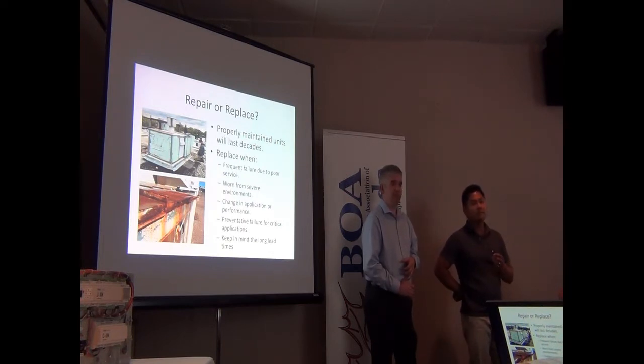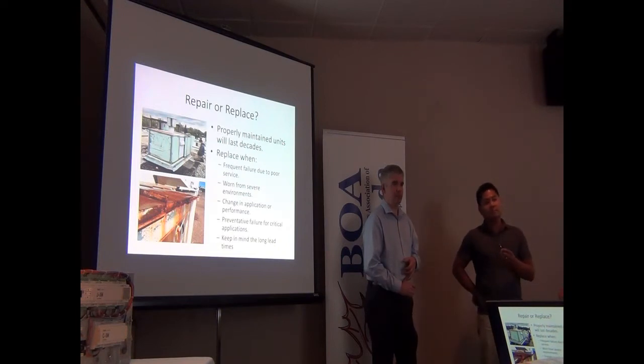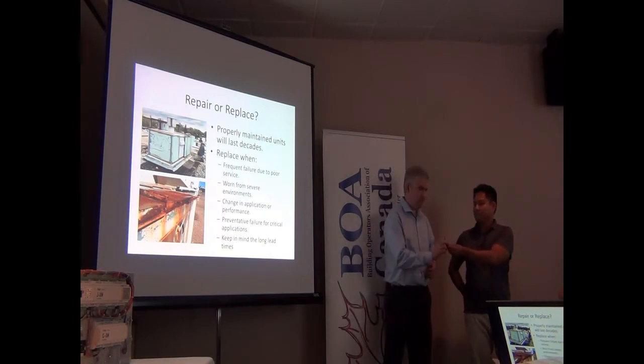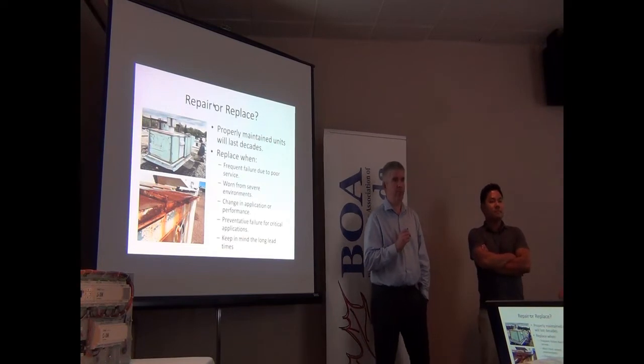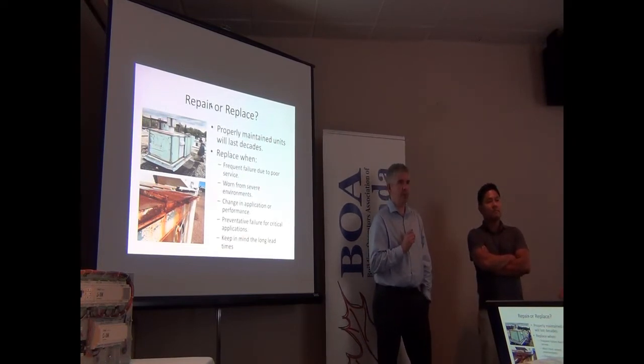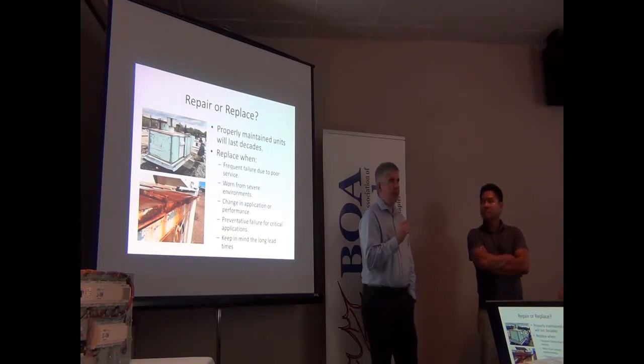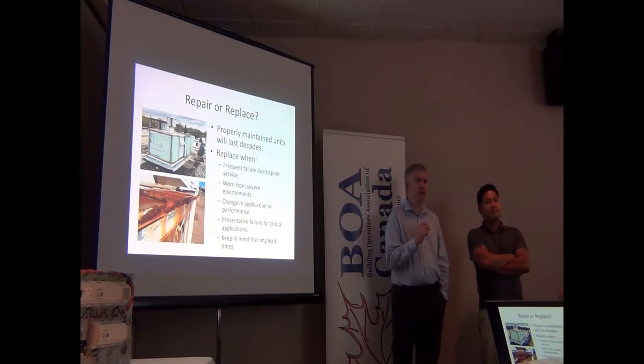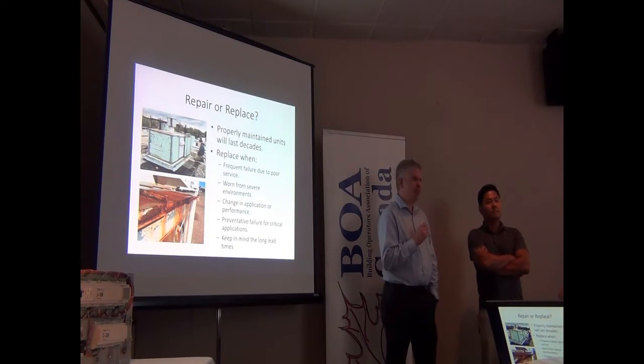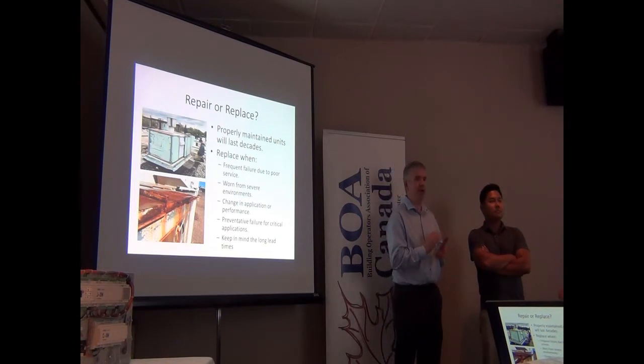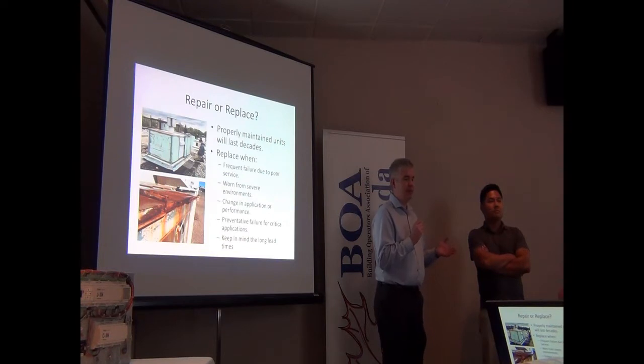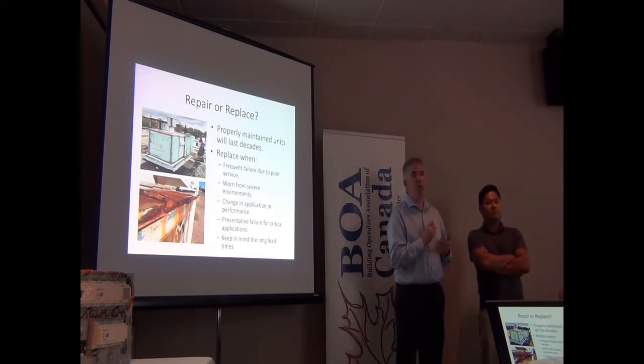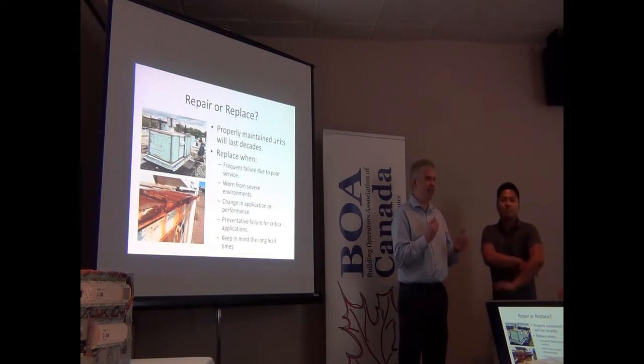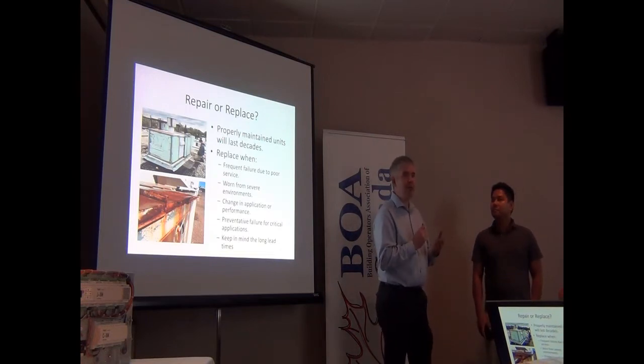You were talking about making changes to peripheral equipment. A lot of building operators have been increasing the filter MERV sizes, which could put some stress on the motors ahead of time—would that be a good idea to call you about? Would that be a voidable item on your warranty list? It probably wouldn't be voidable so long as they're comparable in nature. A lot of units ship with a MERV 8 filter by default, which is pretty standard, but with COVID a lot of people have looked at using MERV 13. It adds a bit more static, but generally the units are designed with a 10-15% buffer in allowed horsepower, as well as naturally stepping up in size. So say a unit requires 9 brake horsepower—you'd want at least a little over 10, and the next size of motor is 15, so maybe you're already in a safe spot.